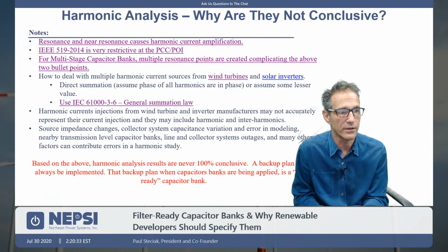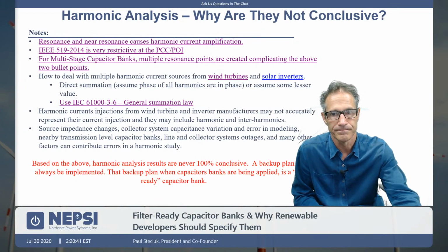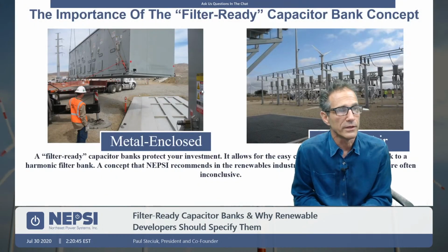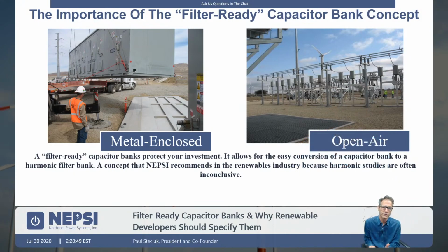The backup plan when capacitor banks are applied is a filter-ready capacitor bank, and that's what we recommend. So, in concept, why is this important? Well, you're going out, you're purchasing either a metal enclosed capacitor bank or an open rack system, and this is a multi-stage capacitor bank.